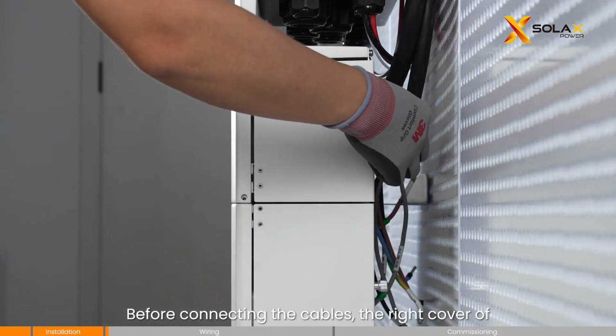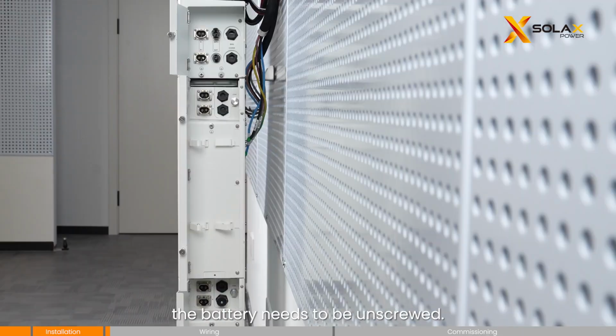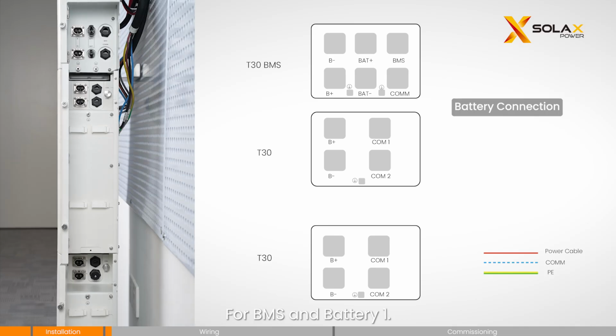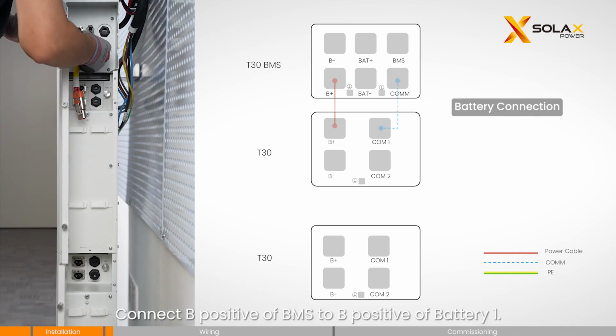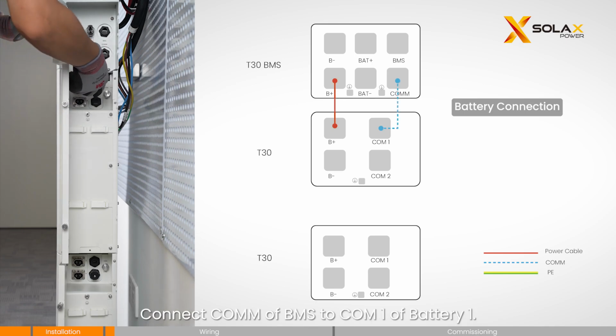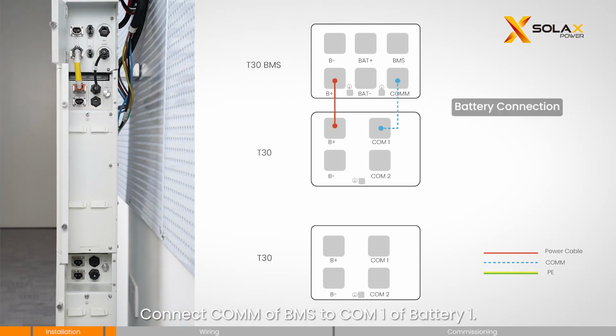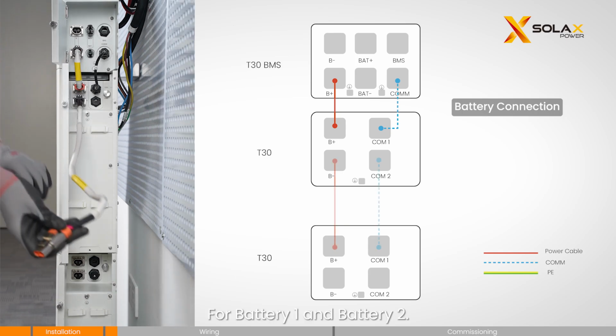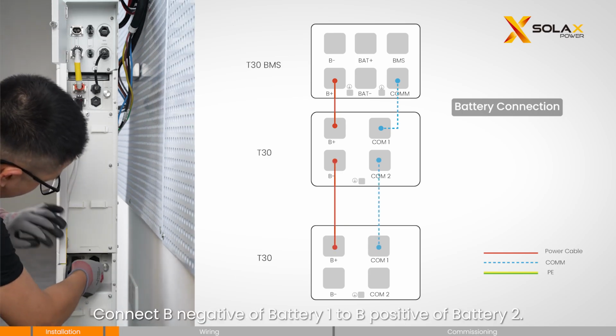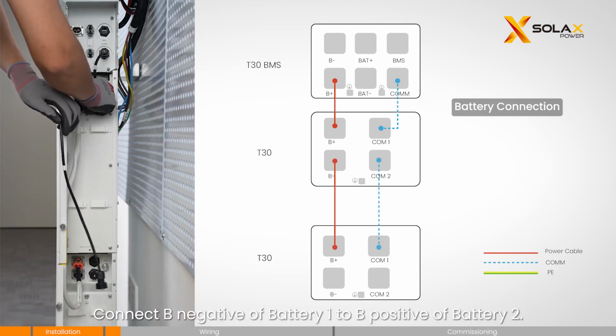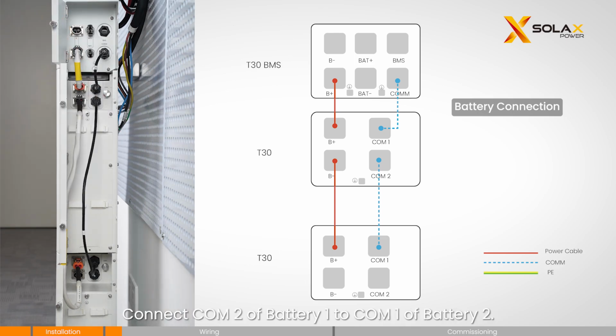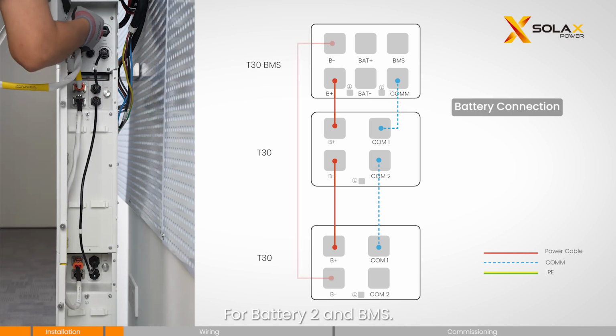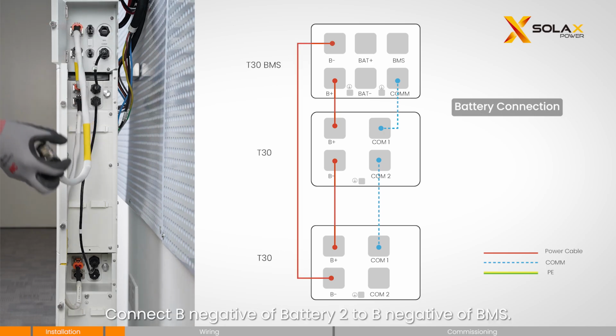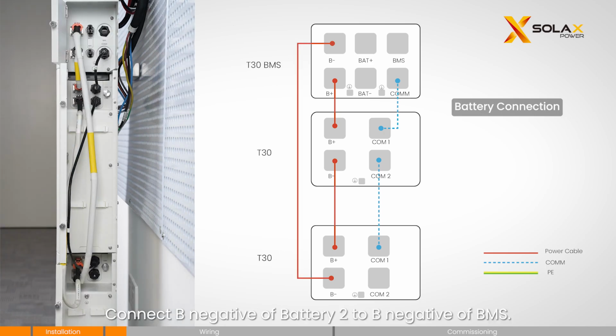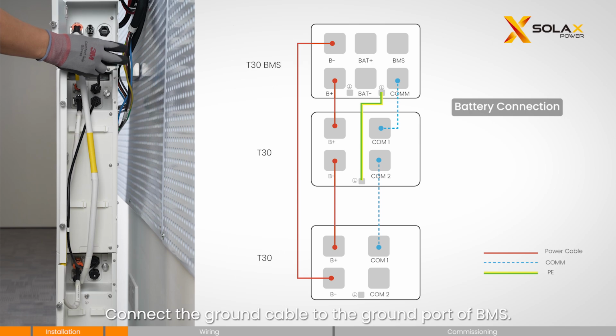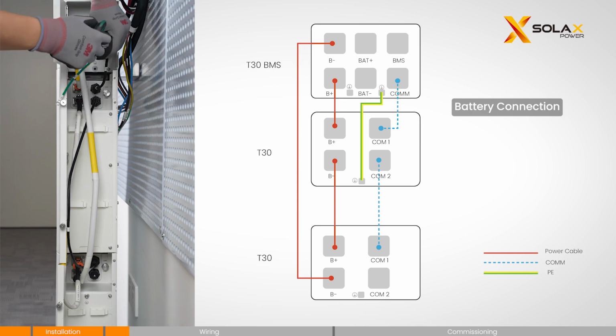Before connecting the cables, the right cover of the battery needs to be unscrewed. For BMS and battery 1, connect B positive of BMS to B positive of battery 1. Connect COM of BMS to COM 1 of battery 1. For battery 1 and battery 2, connect B negative of battery 1 to B positive of battery 2. Connect COM 2 of battery 1 to COM 1 of battery 2. For battery 2 and BMS, connect B negative of battery 2 to B negative of BMS. Connect the ground cable to the ground port of BMS.